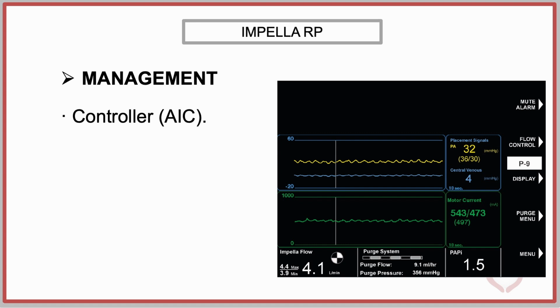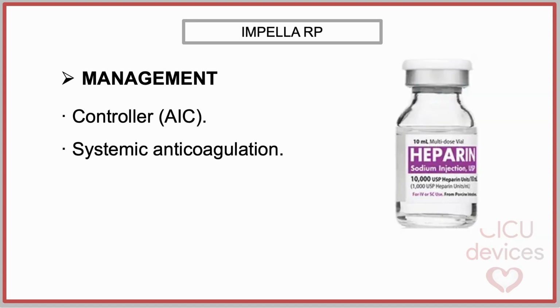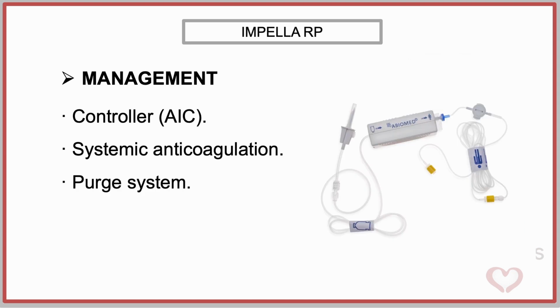Support is adjusted using performance levels or P levels, which regulate pump speed and flow. Adjustments are usually guided by clinical response, central venous pressure, pulmonary artery pulsatility index, and end organ perfusion. Systemic anticoagulation is mandatory to prevent thrombosis within the catheter, with alternatives considered in cases of heparin intolerance. The purge system is also essential to therapy because it creates a pressure barrier that prevents blood from entering the motor. Standard purge fluid is dextrose solution with heparin, and if heparin is contraindicated, sodium bicarbonate may be used instead. Saline should never be used in the purge system.